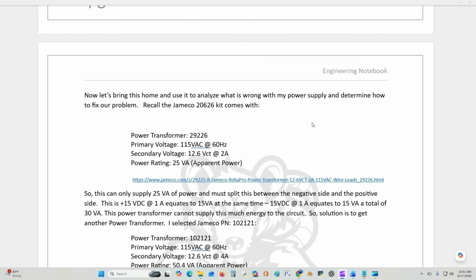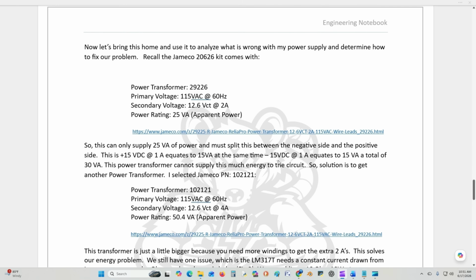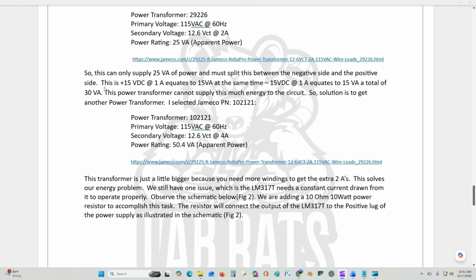You divide that by 2, that's 12 volt-amps on either side. So we were trying to get 2 amps at 10 volts, that's 20 volt-amps. This can only do 12 volt-amps on either side. You can look that up and see the JAMECO specs for that transformer. So we picked out the 102-121 power transformer. It has 115 volts AC in at 60 hertz, 12.6 volts center tap, exactly the same, but at 4 amps per side. So that's 25 volt-amps on either side, with a total rating of 50 volt-amps of apparent power.